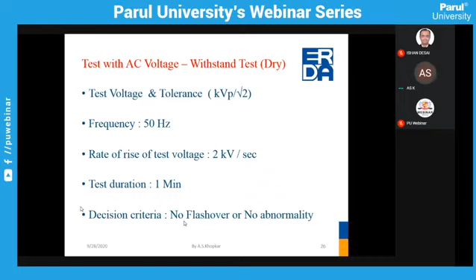As I told you, this test is conducted to check the temporary overvoltage withstand capability. Now, temporary overvoltages in the system may last for 30 seconds, 40 seconds, that's all, not more than that. So the standard defines the test voltage duration as 1 minute, that is 60 seconds. And there should not be any flashover while we perform the test, or any other abnormal condition, such as a puncture inside, visible noise or partial discharge. Nothing should be there. Then only can we say the product has passed. If there is a flashover, the panel will automatically trip and we come to know that the product has failed. Sometimes we can also see the flashover or disruptive discharge visibly across the product. That way we can find out whether the product withstands this test or not.